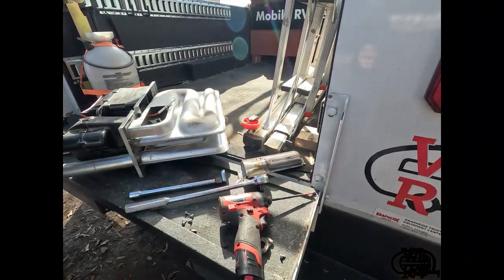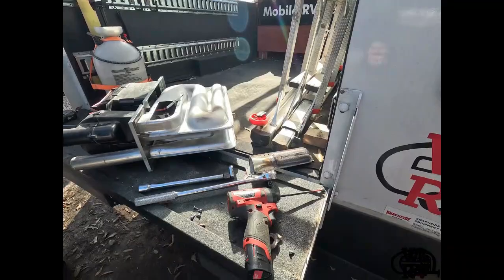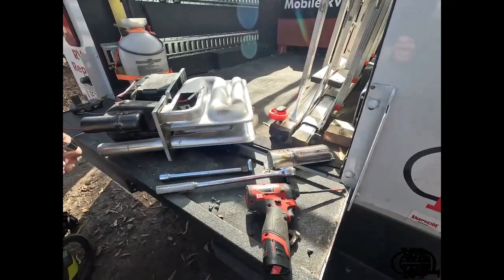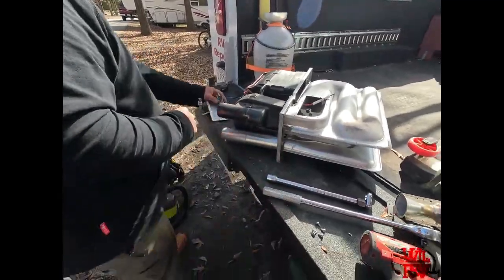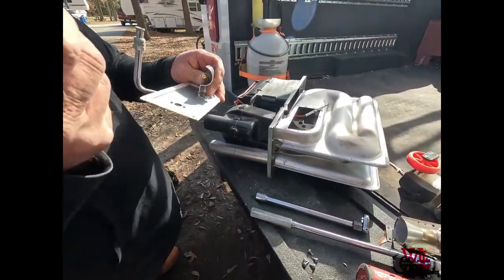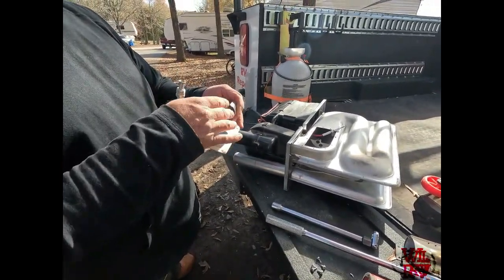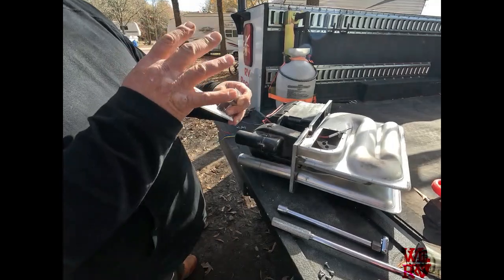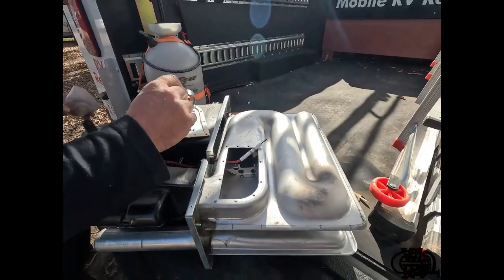I am going to take that orifice off and just make sure there ain't nothing inside, just do our due diligence. So I just take a small socket. Yeah. Take that off there. Nothing metal in that hole. If you got a thin toothpick or something, you could do that. But they say because of that brass, I don't know how exact it has to be. Don't put anything metal in that hole. Here we go.